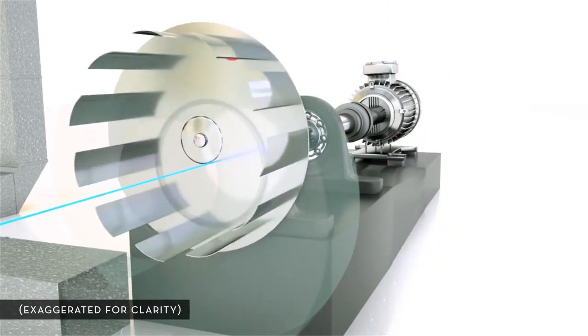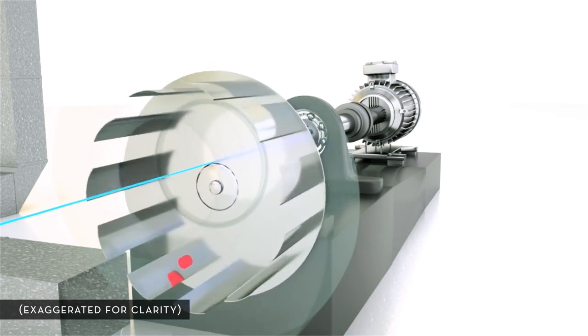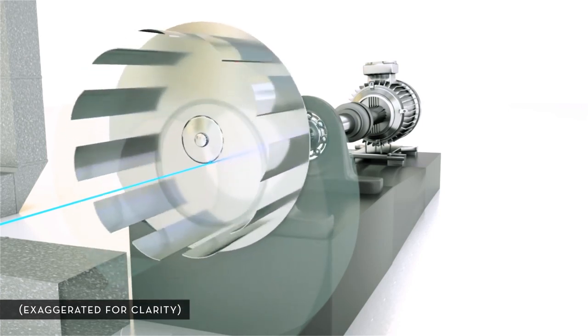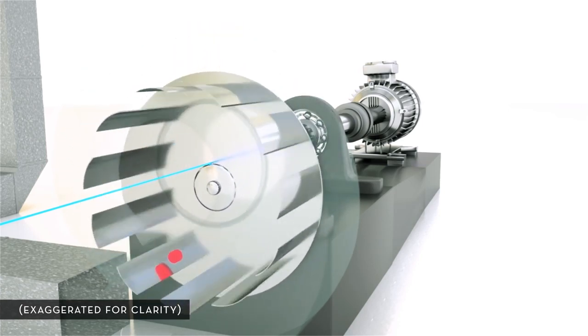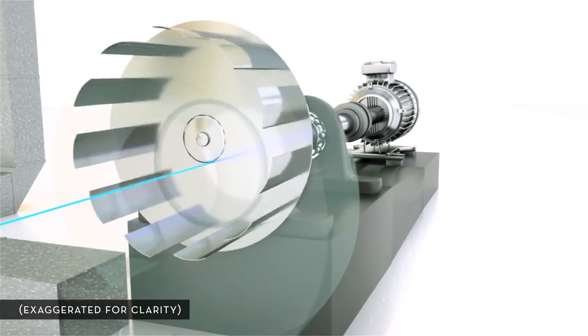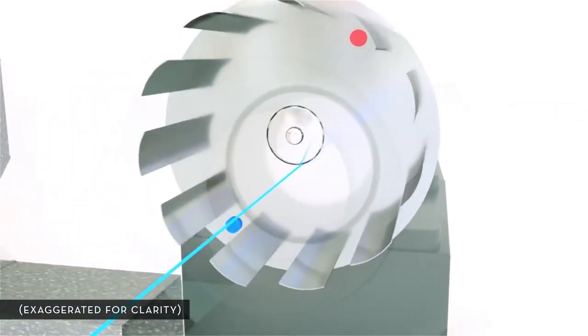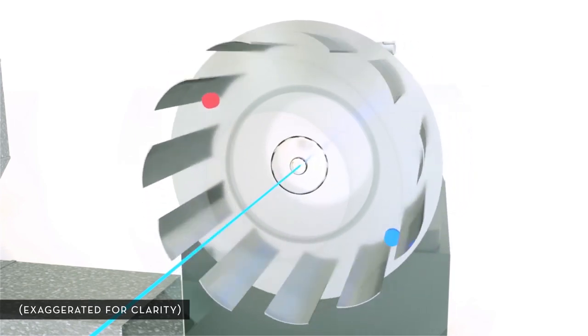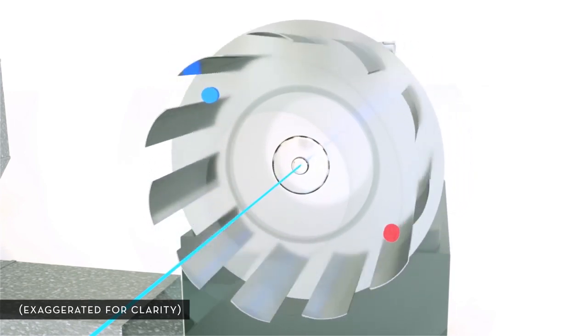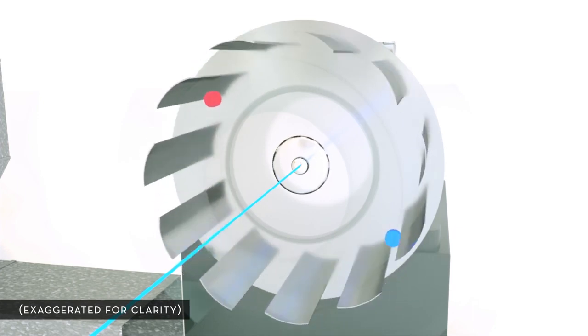Similar to the process an auto mechanic employs to speed balance the tires of a car, rotating machinery is balanced by either adding weight to the light spot or removing weight from the heavy spot. In this illustration, we will add weight to counterbalance the heavy spot so that mass is evenly distributed around the axis of rotation.